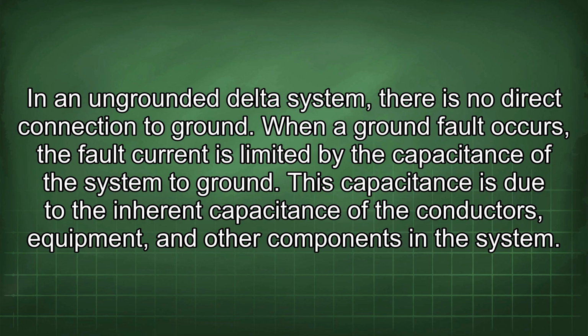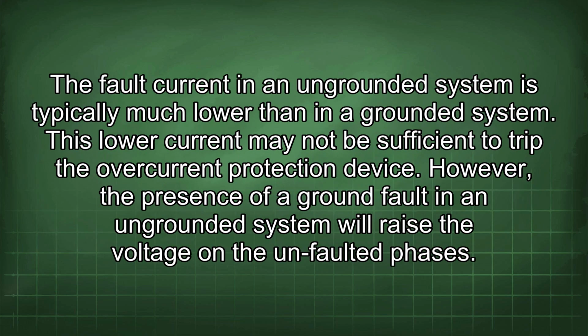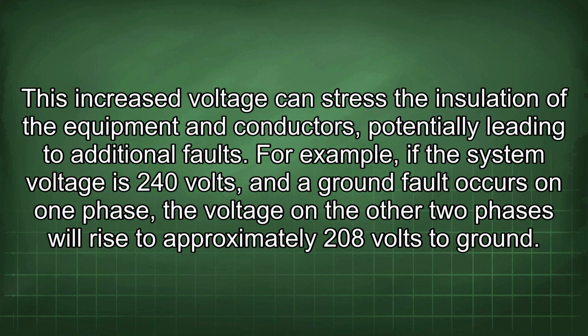This capacitance is due to the inherent capacitance of the conductors, equipment, and other components in the system. The fault current in an ungrounded system is typically much lower than in a grounded system. This lower current may not be sufficient to trip the overcurrent protection device. However, the presence of a ground fault in an ungrounded system will raise the voltage on the unfaulted phases. This increased voltage can stress the insulation of the equipment and conductors, potentially leading to additional faults.